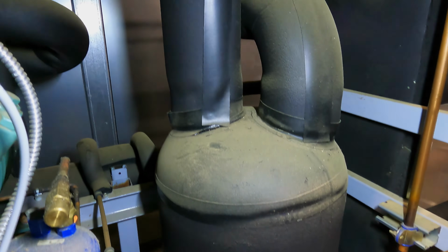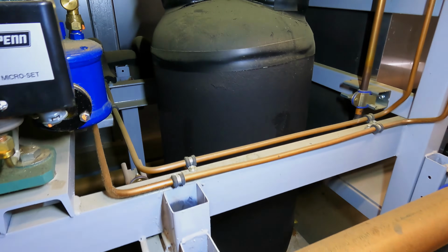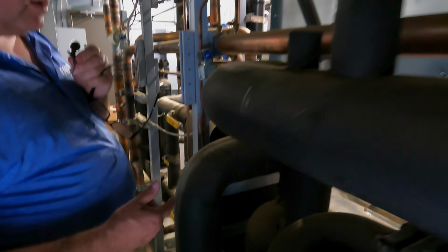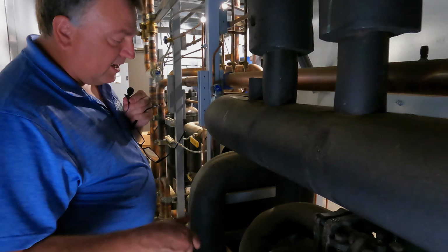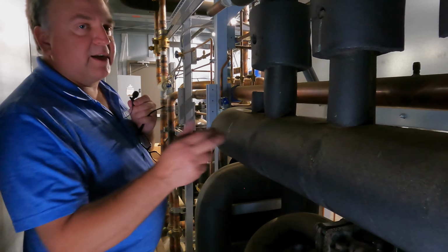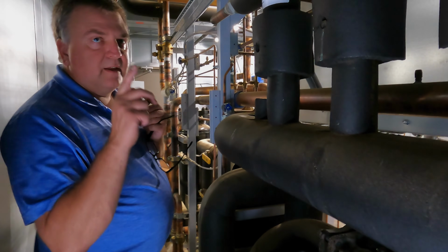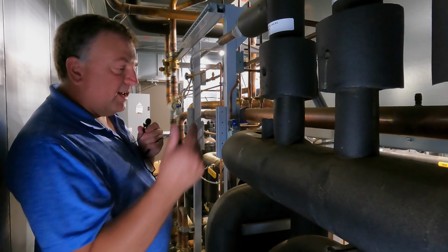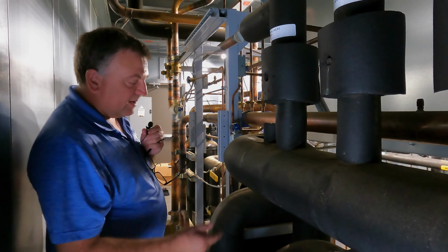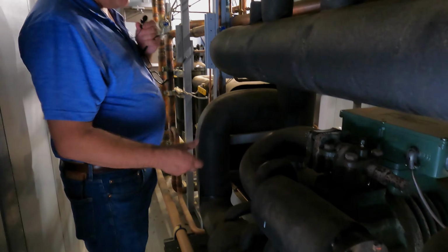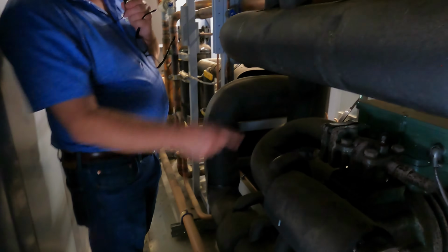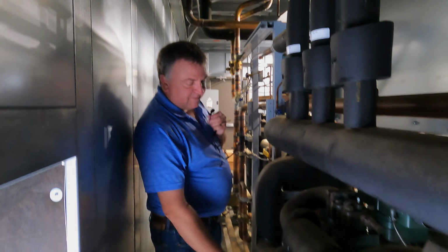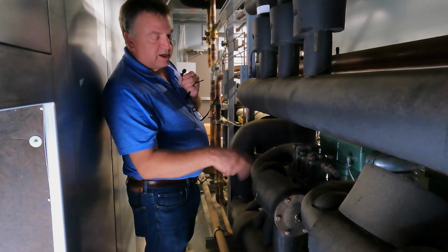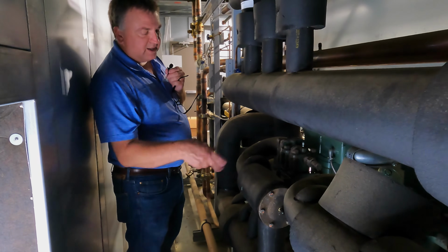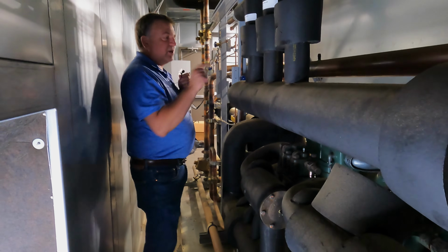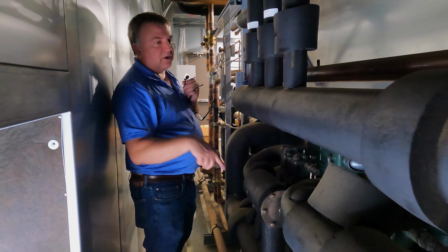Now that's an accumulator. You don't want to confuse it with a receiver or a holding tank or anything. All it does is, hey, maybe I had some liquid coming back and I didn't boil everything off in my chillers. If I didn't boil anything off and I got a little bit of liquid come back, this will drop it in there, help the evaporator, and just pull straight vapor suction to protect our compressor. Now we've got vapor coming back in, and we start the process all over again. The compressor compresses, becomes a high discharge, sends it out to the condenser, and it just circulates over and over again.